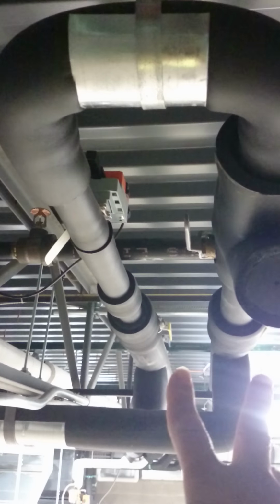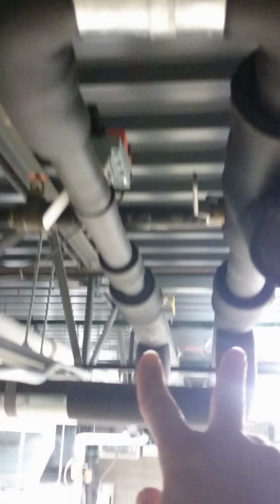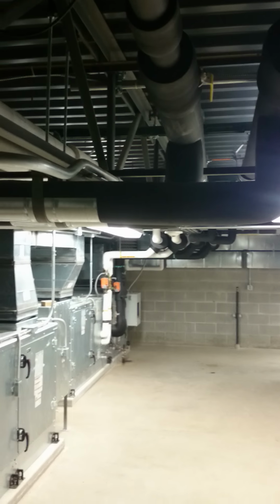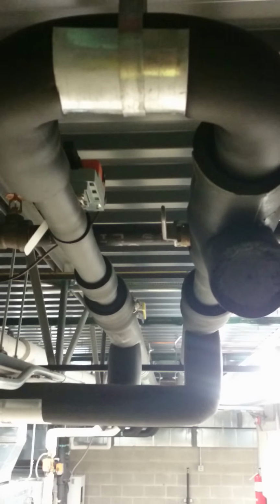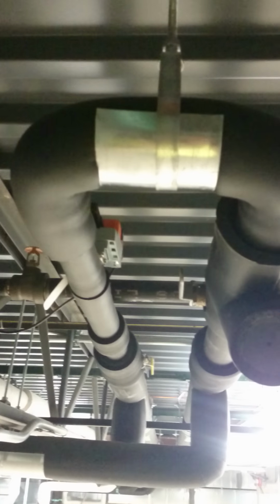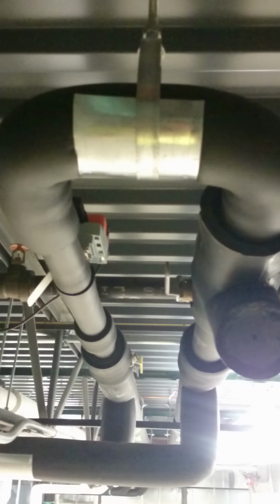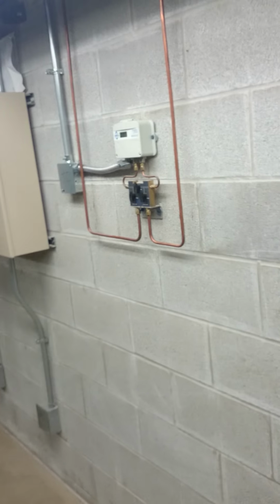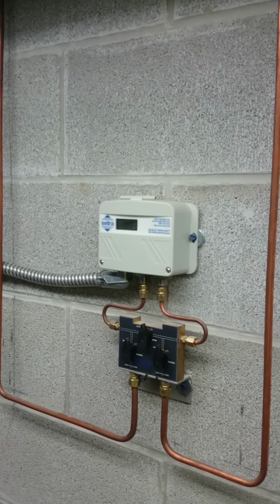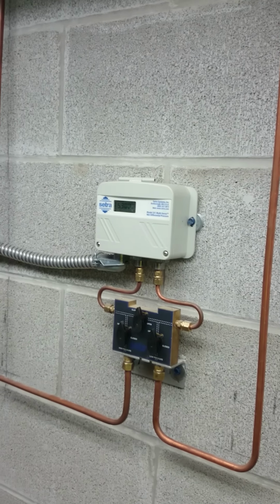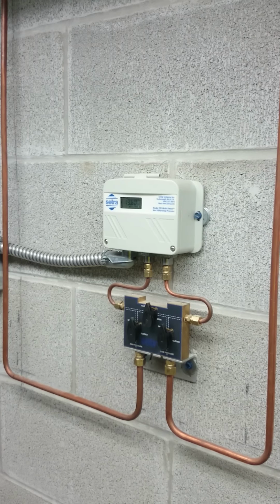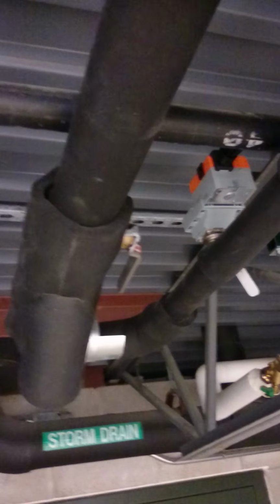So I found at that time this bypass circuit wasn't installed. So we just had two caps at the end of this. So when all the actuators shut down, we basically had no flow through the system. So we were contracted to come out and install this bypass circuit. So per their control system here, as their differential pressure transducer here senses that enough valves are closed to where we don't have any flow, we're going to start modulating this bypass open.